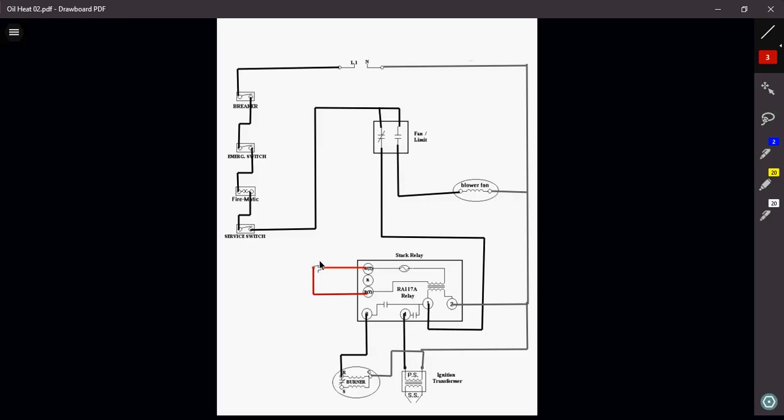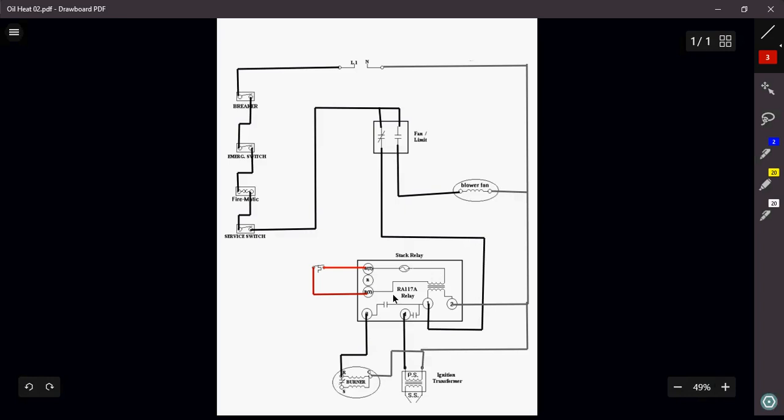Thermostat calls for heat. That's going to close. That's going to energize the coil, which is going to close my terminals 3 and 4, which will bring on my burner sequence. Furnace is going to light as long as everything is correct and good to go. After approximately, we'll say, about 90 seconds, the stack relay will know that it lit.